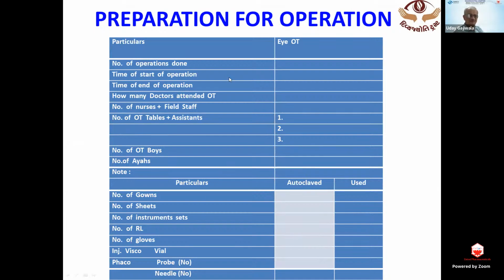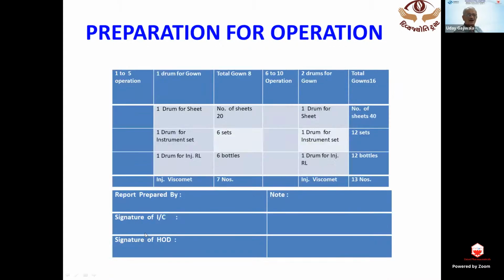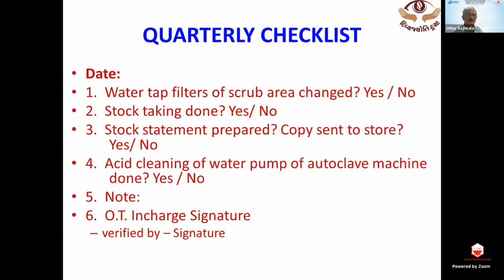So the top tells us about the activities done on that particular day, and the bottom, how much of linen, etc., instruments and irrigating fluid, viscoelastics, etc., were autoclaved. How much material has been put in one drum is also to be ensured, because Dr. Purvasha also showed us tight packing is not a good idea, and in that case, steam penetration will not occur properly. So we have to do a loose packing, and that's where how many items are sterilized in one particular drum is important, and that needs to be monitored.